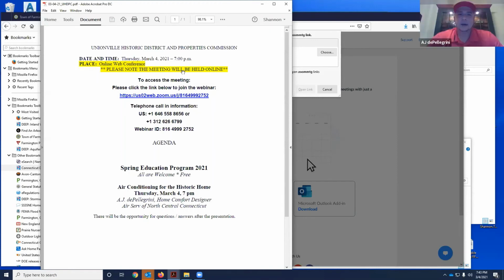The biggest thing is let them breathe. You don't want really anything within 18 inches of the face, and also serviceability. Making sure that our techs, when they come there, aren't trying to dig through the jungle to get back to the unit. Good point. It's just things to be aware of. And lattice is a very good idea. I know Ted had talked about some kind of fake beehive or something like that. As long as air can move, you can put whatever you would like around it.